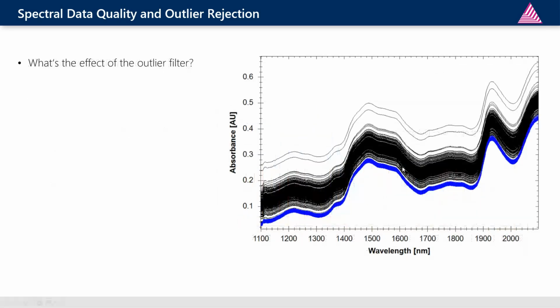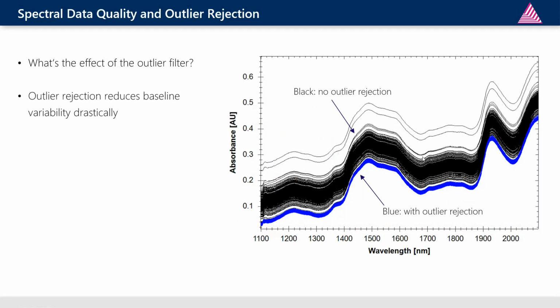Okay, what's the effect of the outlier rejection if I use it or if I don't use it? Here you can see two instruments. One of the two in this trial had outlier rejection turned off, while the other unit had the outlier rejection turned on for one process test only. You can see the unit with the outlier rejection turned on provides a really stable and really low baseline, while the instrument with outlier rejection not turned on has a much higher variation in absorbance values in baseline.